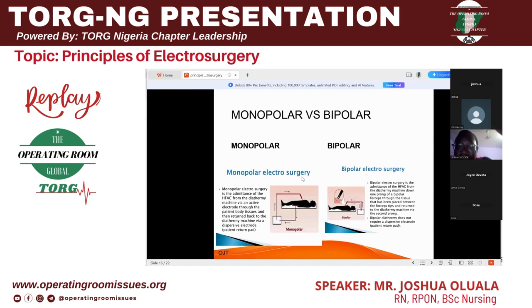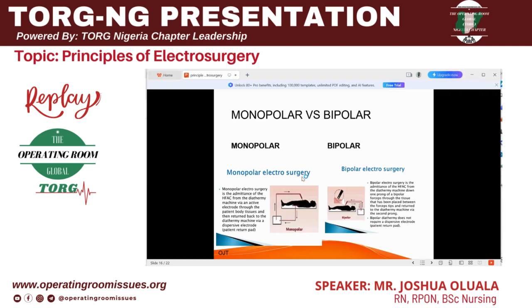We can see the picture. We can see the electrosurgical generator, and we can see how the current travels to the patient. We can see the return electrode and the flow of the current. But in the case of bipolar, we can see that everything comes from the generator to the patient's tissue, and also back to the generator.